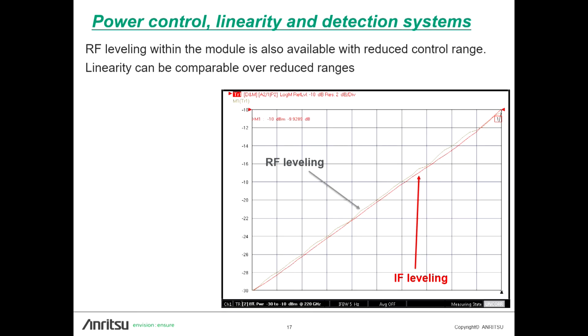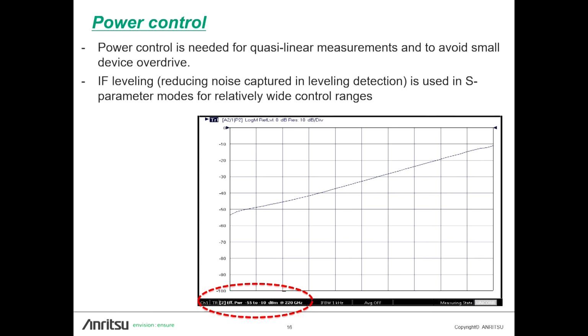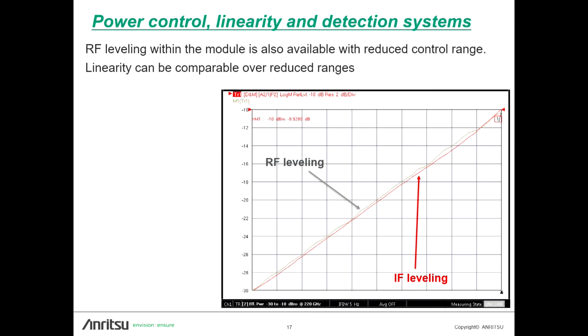Now, that was with IF leveling, this previous chart, so you're required to have some kind of frequency plan that's commensurate with that to generate an IF. But oftentimes when you're measuring at least certain frequency conversion devices, you may not have an IF available. So there are RF leveling taps in all of the paths, which, because they're broadband, there isn't nearly as much control range available. This is only over -30 to -10, but you get reasonable agreement between the two, just natively from that.